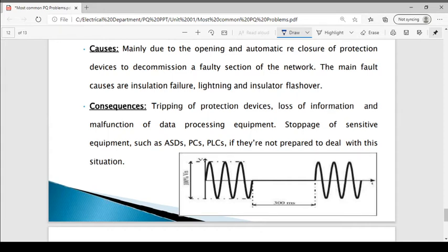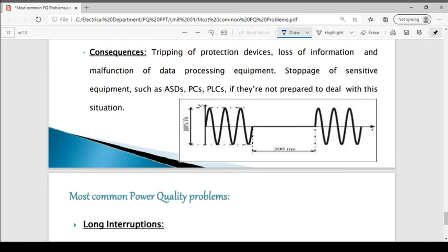What are the consequences? The tripping of the protection devices, loss of information and malfunctioning of the data processing equipment, and stoppage of sensitive equipment such as AC/DC drives, PLCs, PCs. So these are certain consequences of a very short interruption.